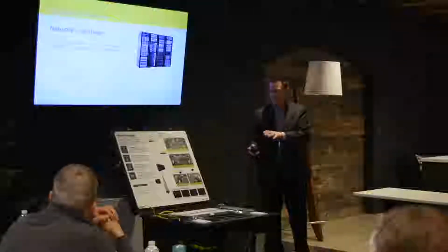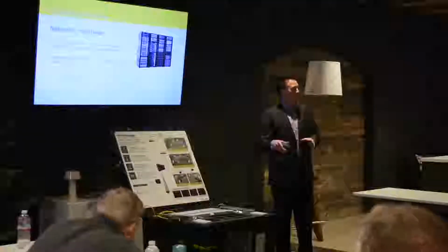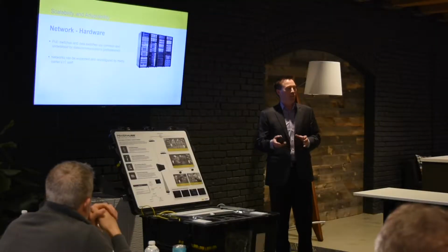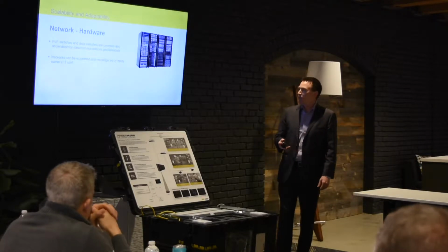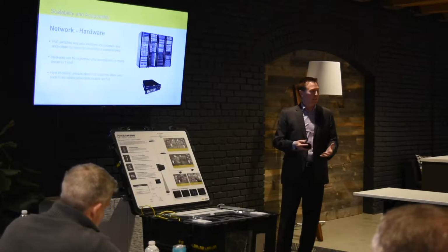So on the hardware side, you have the PoE switches. So basically just thinking about all the different components here. You have PoE switches, which is kind of buried inside this box right here. And then it could also be mid-span, so you can choose whatever switch you want. It doesn't also have to be a PoE switch. You can choose a non-PoE switch and put what's called a mid-span, and it just injects power over that Ethernet line. So it's more flexible. You can choose whatever brands you want at that point. And it's standard IP and IT type of equipment.